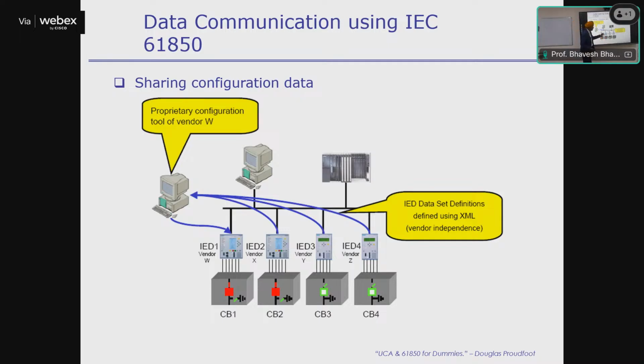So, for example, one of the IEDs goes bad. Its functionality can be transferred to another IED, or a spare IED, and you can do that through configuration. Because remember the logical nodes—logical nodes are the ones that provide functionality to any IED. So if you can just change the logical node, then you can change the functionality.